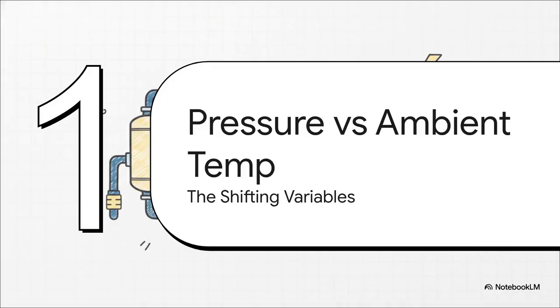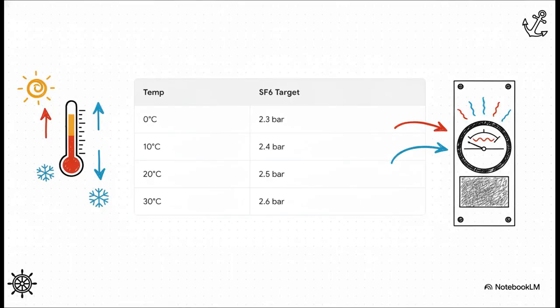Section 1. Pressure versus ambient temperature. The shifting variables. Okay, let's dive into this. Because as you know, out on the water, temperatures are all over the place. Whether you're freezing in the North Sea or sweating it out in the Gulf of Mexico, the heat of your environment absolutely dictates the gas pressure inside that sealed breaker pole. You can't just memorize one number and call it good.